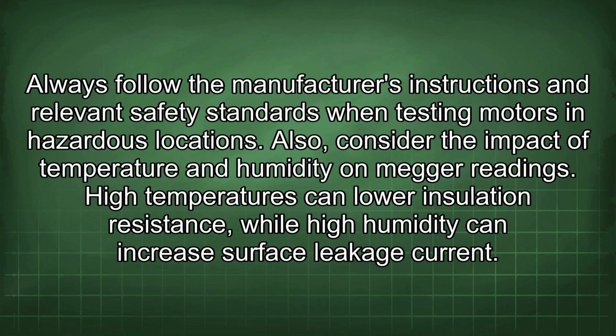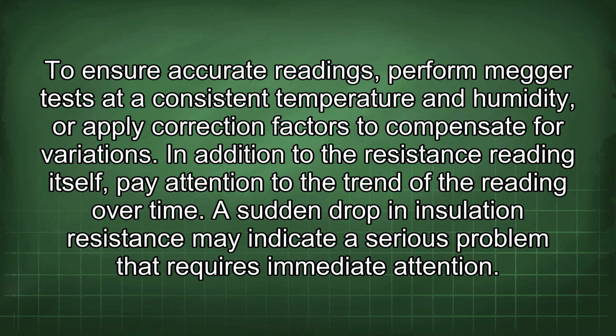Also, consider the impact of temperature and humidity on Megger readings. High temperatures can lower insulation resistance, while high humidity can increase surface leakage current. To ensure accurate readings, perform Megger tests at a consistent temperature and humidity, or apply correction factors to compensate for variations. In addition to the resistance reading itself, pay attention to the trend of the reading over time.